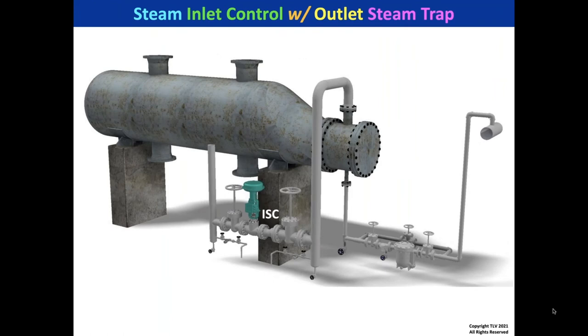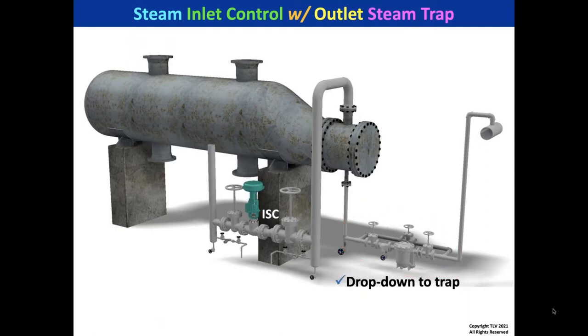Let's take a further look at a kettle reboiler with an outlet steam trap. In addition to sizing and selecting the trap, I'd like you to consider installing a drop-down to the trap, a float trap as the preferred trap type, and a check valve at the outlet. I'm going to explain those three recommendations.